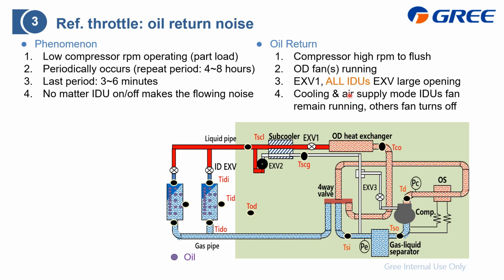All indoor units. The reason is that the compressor is at high RPM, which also indicates the refrigerant flow rate is very high. So we need to make all of them open to allow the large refrigerant flow rate to go through. And if this refrigerant impacts the indoor unit EXV, it also makes noise. And if this indoor unit is turned off, which means there is no other noise to cover this impact noise, it makes this noise significant.